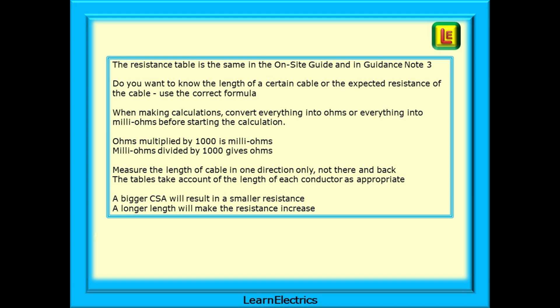A brief summary. The resistance table is the same in the on-site guide and in guidance note three. Do you want to know the length of a certain cable or the expected resistance of the cable? Be sure to use the correct formula to calculate this. When making calculations convert everything into ohms or everything into milliohms before starting the calculation. Ohms multiplied by 1000 is milliohms and milliohms divided by 1000 gives ohms. Measure the length of the cable in one direction only not there and back as the tables take account of the length of each conductor as appropriate and a bigger CSA will result in a smaller resistance whilst a longer length will make the resistance increase.